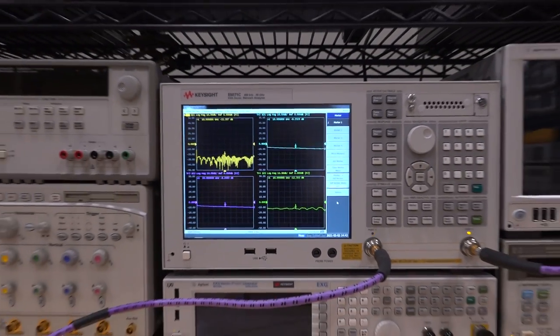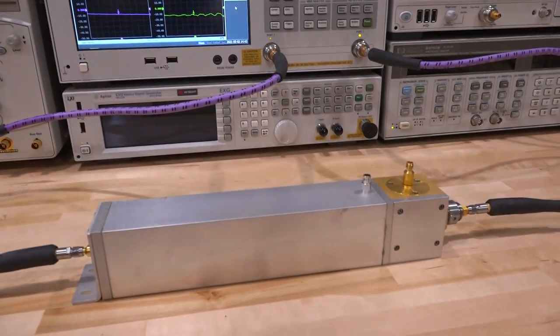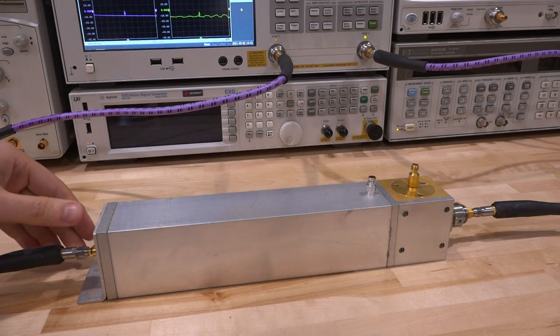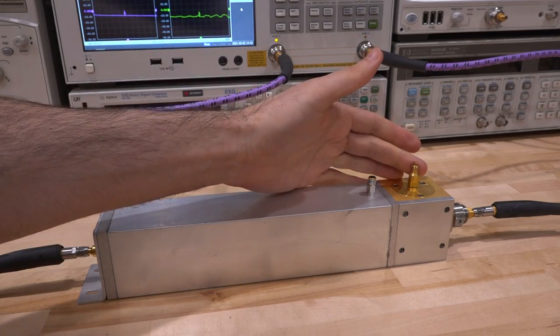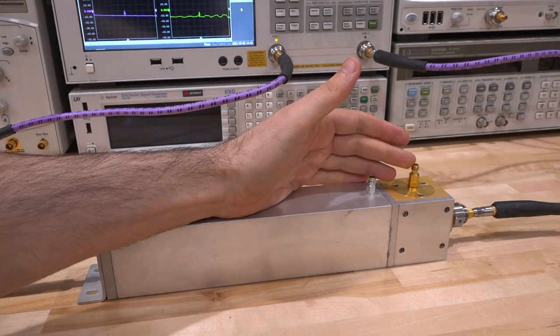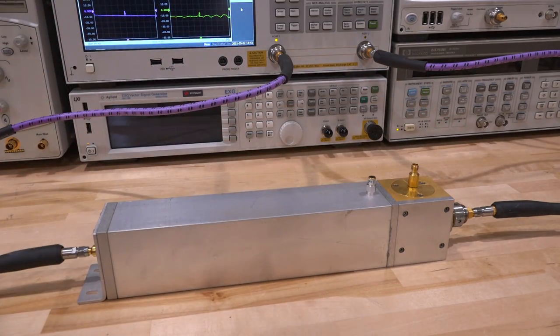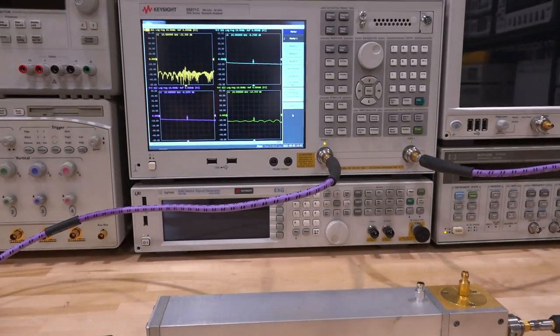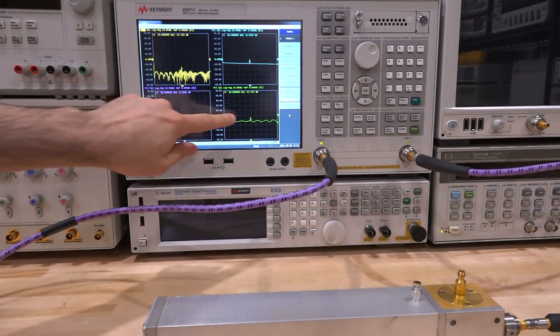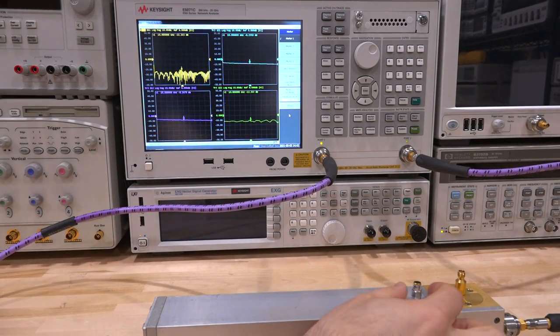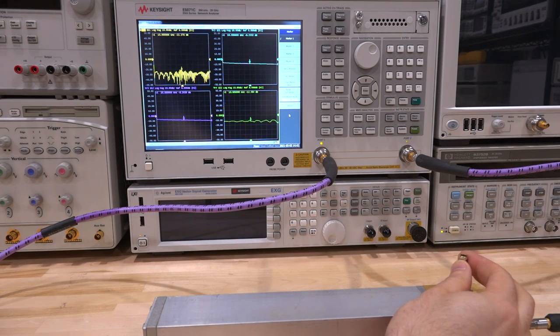But why do these not match? Well, this actually tells us something really important about the property of this coupler. It basically tells us that in this coupler we have very good isolation between this port and this port. Because the unterminated port here causes the return loss of this port to be bad, but not of this one. And we can observe this by actually putting the attenuator back.